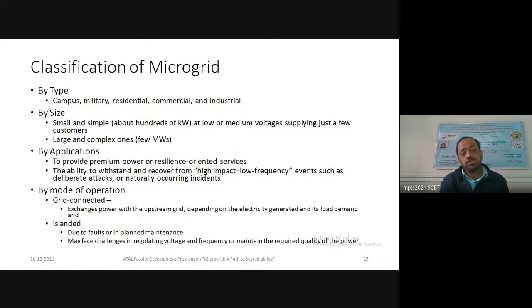Then comes classification by mode of operation. It could be grid-connected, as already discussed, which exchanges power with the upstream grid depending on electricity generated and load demand. If there is surplus generation, the microgrid pumps power into the grid; if there is more demand in that microgrid setup, it may draw power from the main utility grid.